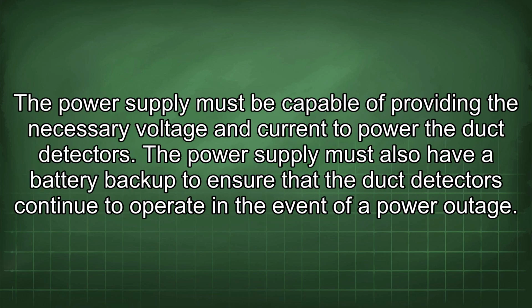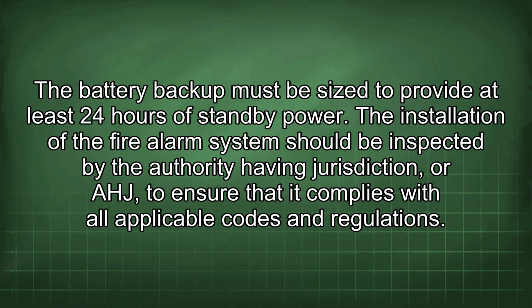The UL fire rated 24 volts DC power supply must be listed for use with fire alarm systems. The power supply must be capable of providing the necessary voltage and current to power the duct detectors. The power supply must also have a battery backup to ensure that the duct detectors continue to operate in the event of a power outage. The battery backup must be sized to provide at least 24 hours of standby power.